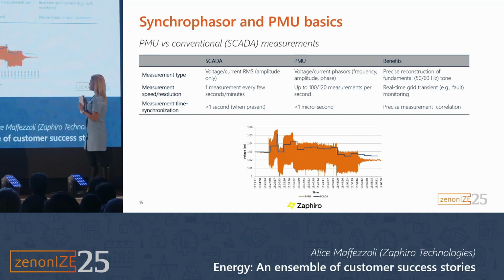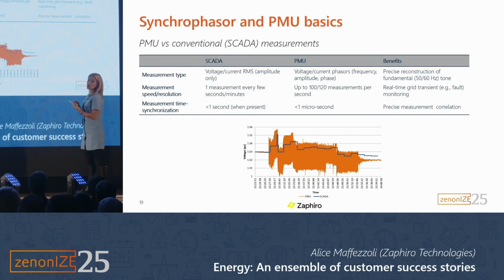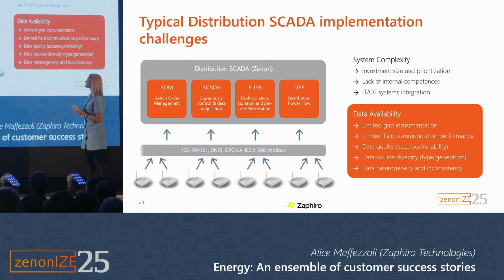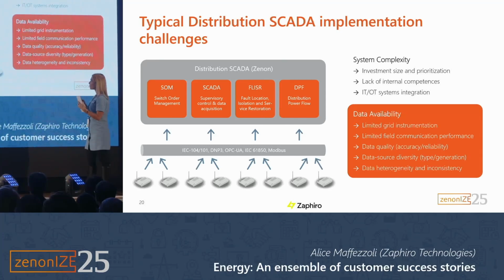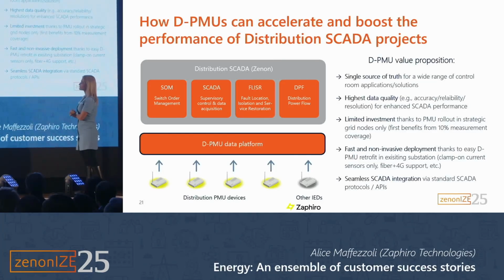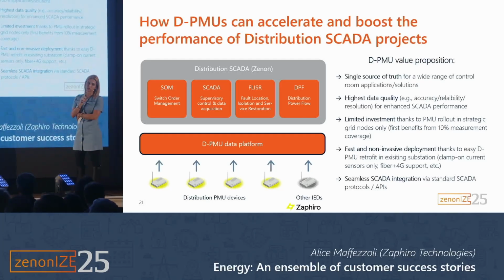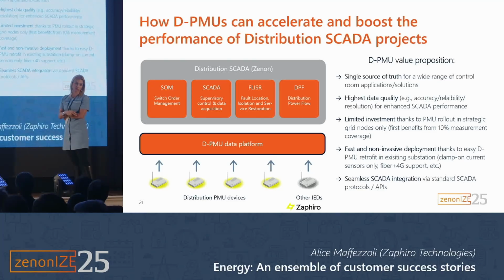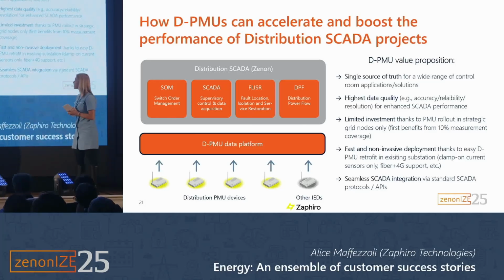The result is a better observability of the grid, so more awareness of what is happening in the grid, and we can also detect transients, which enables us to check power quality events and incipient faults in the grid. So what are the challenges of typical SCADA implementation in distribution grids? In general, it is the system complexity: large investment, a lot of data, limited grid instrumentation, and when this instrumentation is present, it is very diversified. And how can PMU help to solve this challenge? The idea of PMU is to have a few measurement devices installed in critical points of the grid that solve different use cases. This is really the advantage of PMU technology and of a platform that can use PMU measurements: it serves different kinds of use cases and different departments in the same company. But I will go through it in a while.